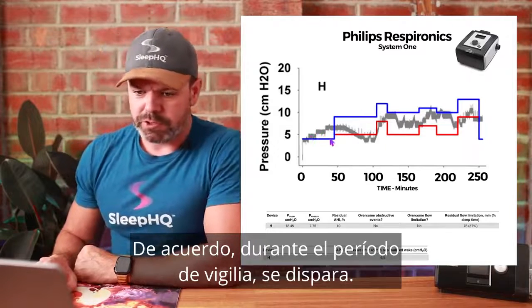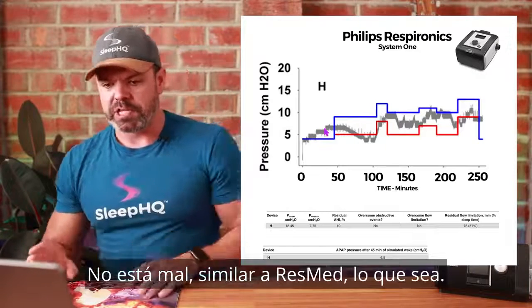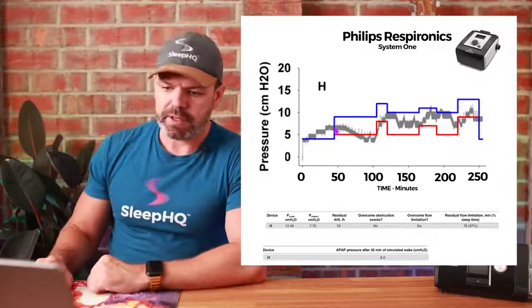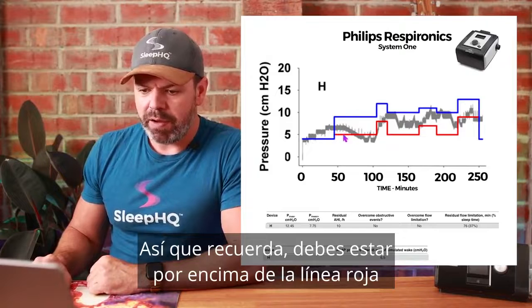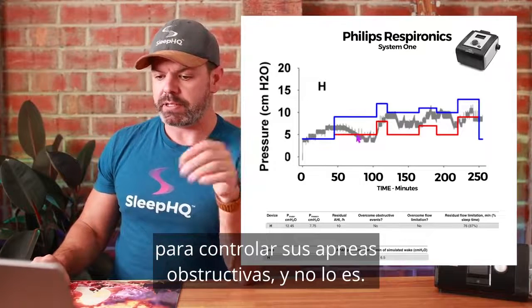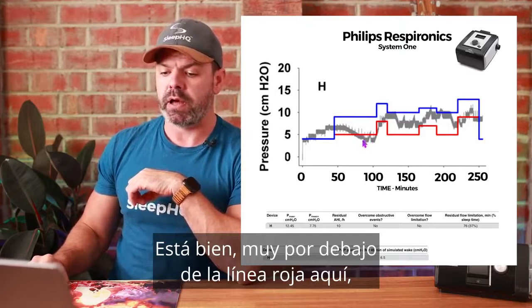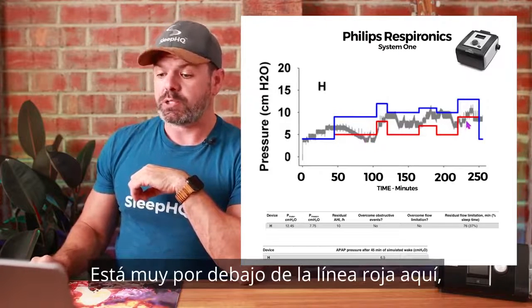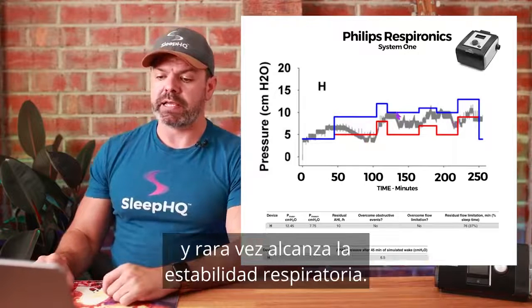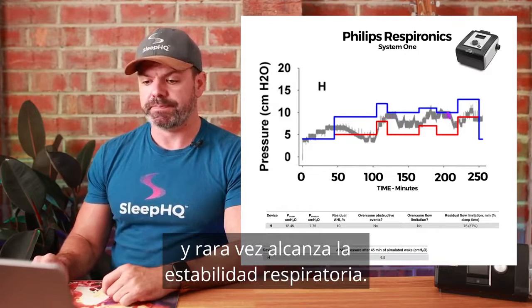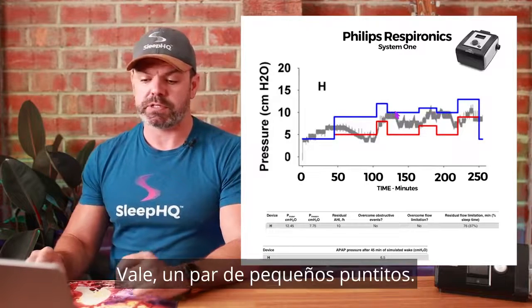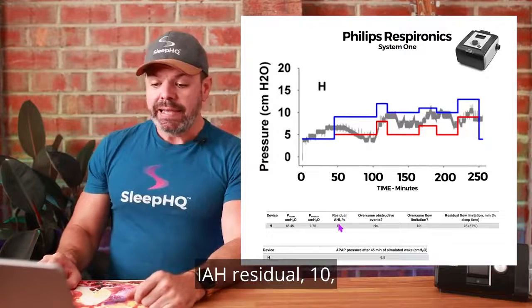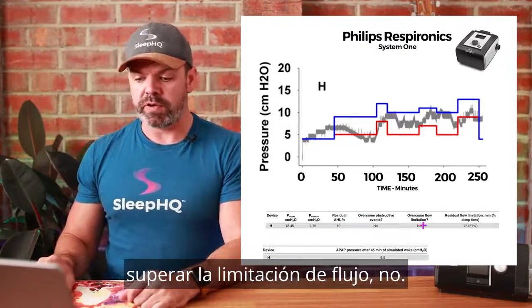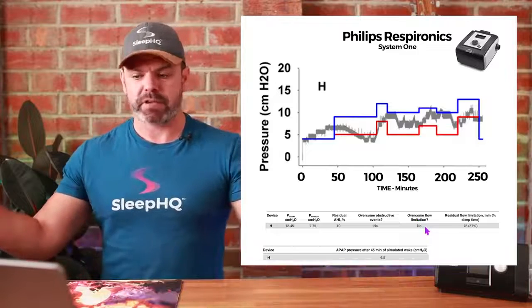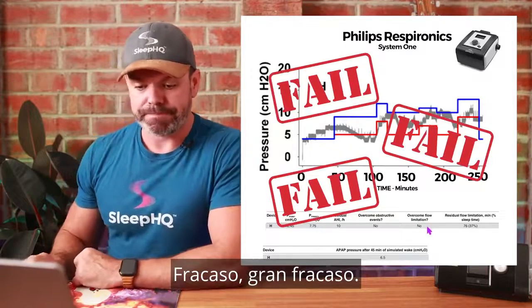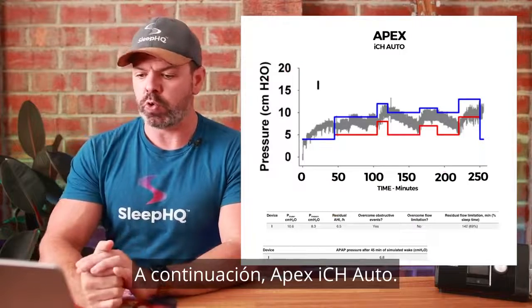Okay, so during the awake period, it shoots up, not too bad, similar to ResMed, whatever, but look at this here. So remember, you need to be above the red line to control your obstructive apneas, and it's not. It's well below the red line here, below the red line here. It's well below the red line here, and rarely does it reach breathing stability. Okay, a couple of tiny little spots. Residual AHI 10. Overcome obstructive events, no. Overcome flow limitation, no. Fail. Big fail.